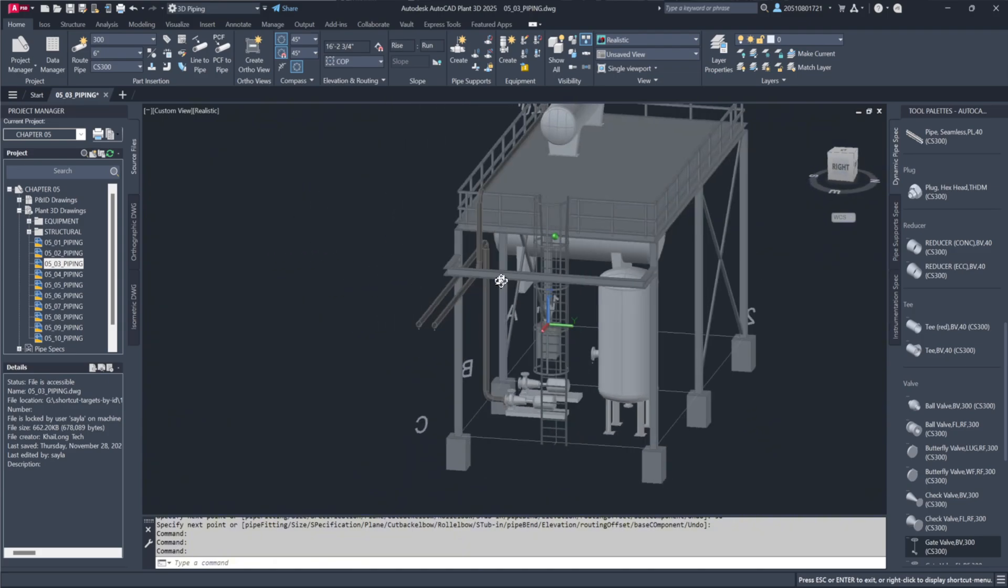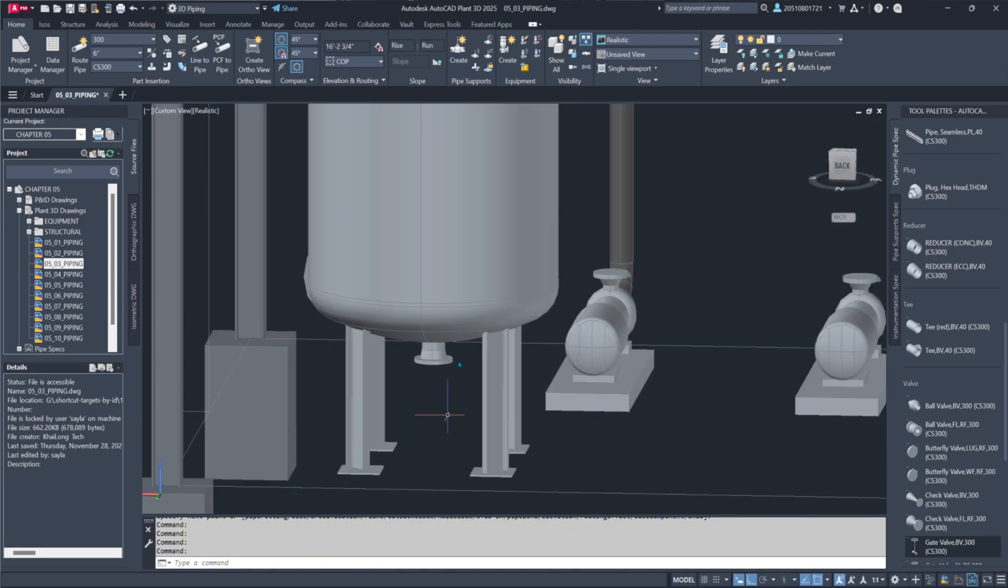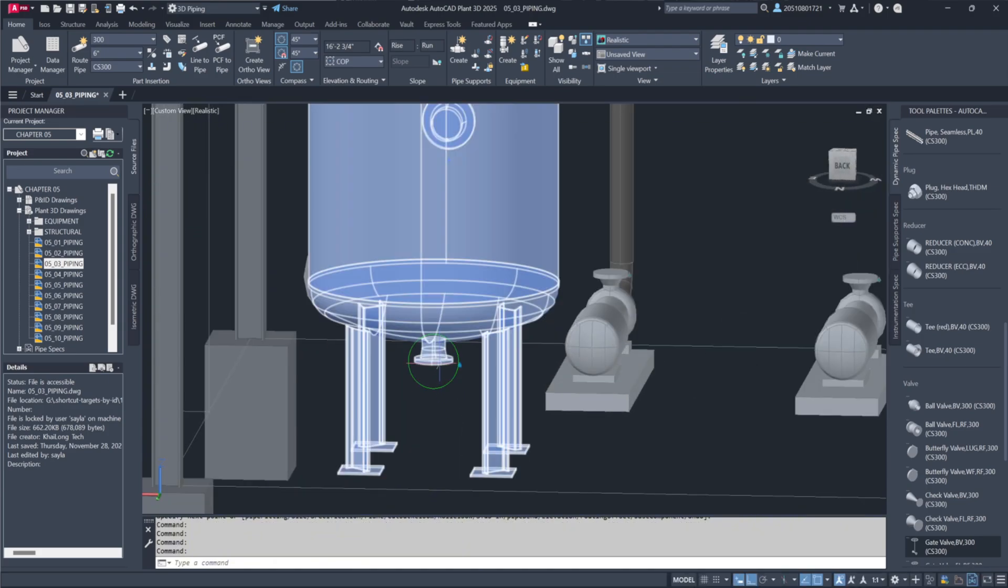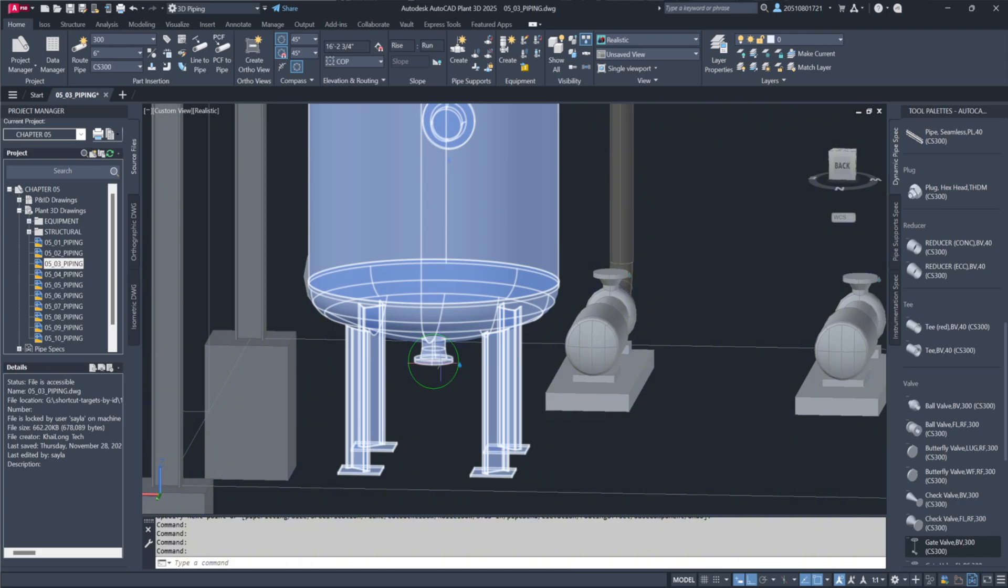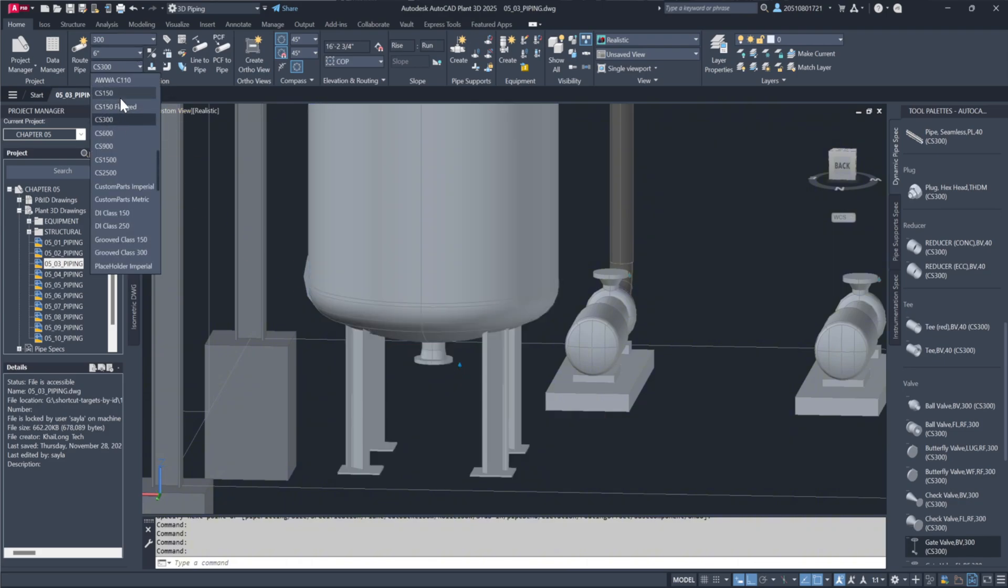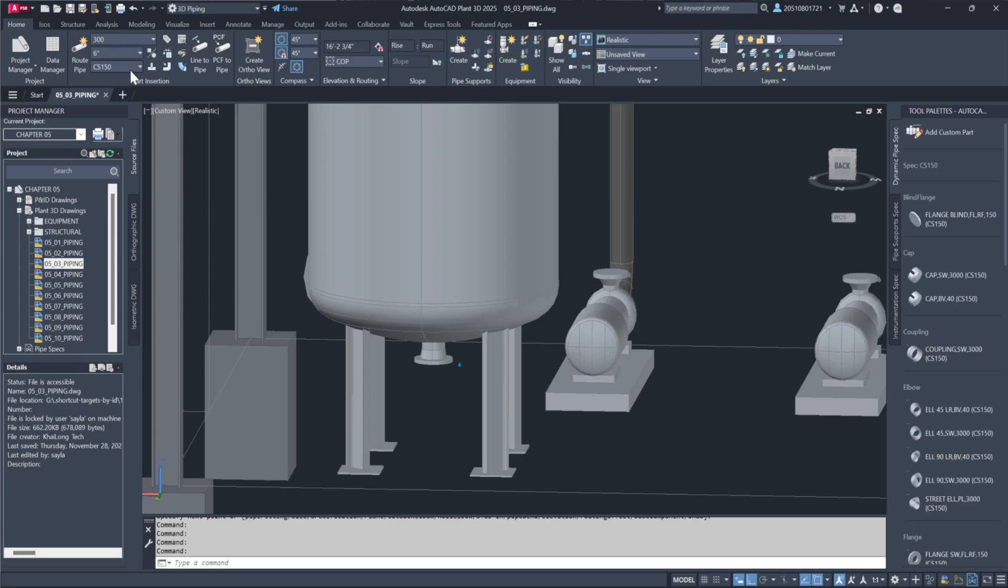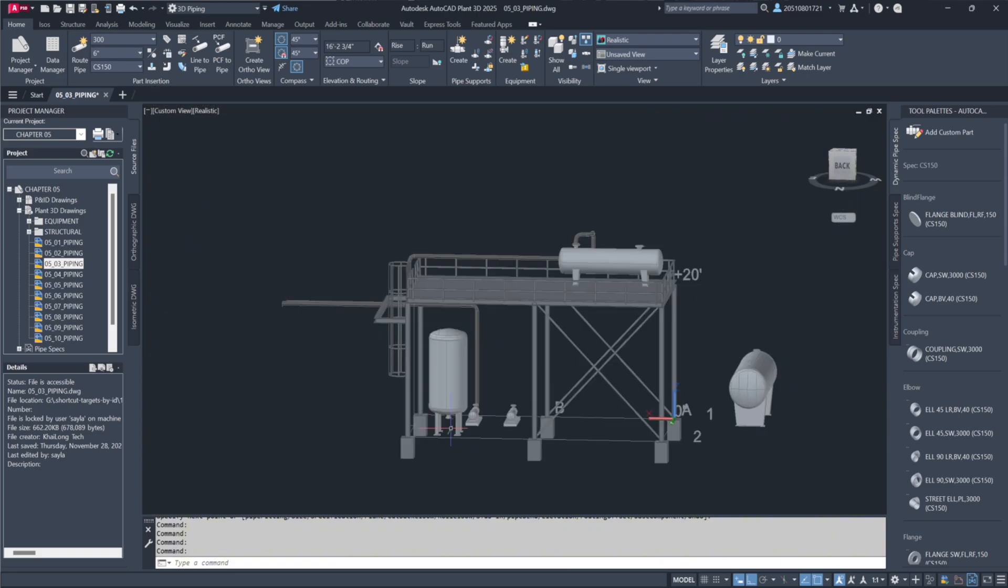For additional configurations, such as connecting to a tank like 503, identify the nozzle details—for example, 6-inch, 150-pound—and adjust the settings accordingly. Set a new line number, such as 400, and use continuation piping to route from the bottom of the tank to the target location, which is the horizontal vessel.